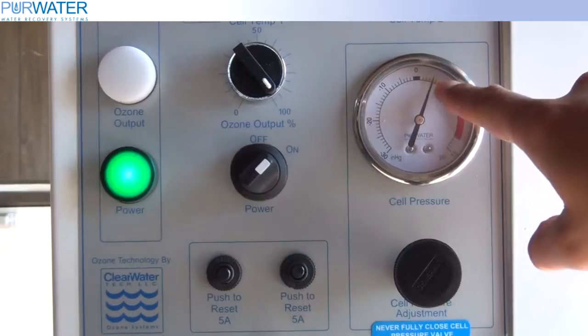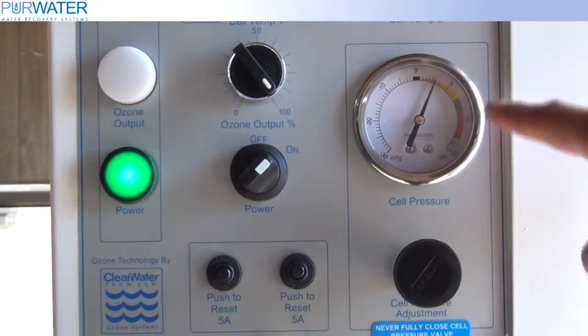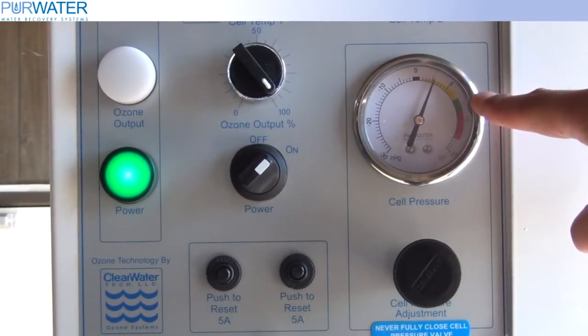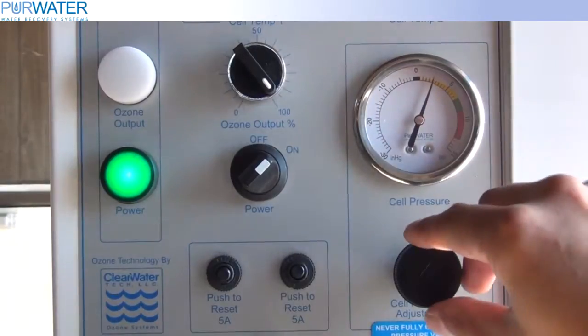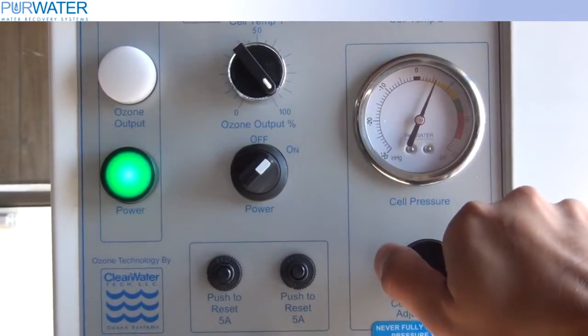To begin, the ozone cell pressure gauge should be set to 8 psi. This can be achieved by closing or opening the cell pressure adjustment valve until you achieve 8 psi.